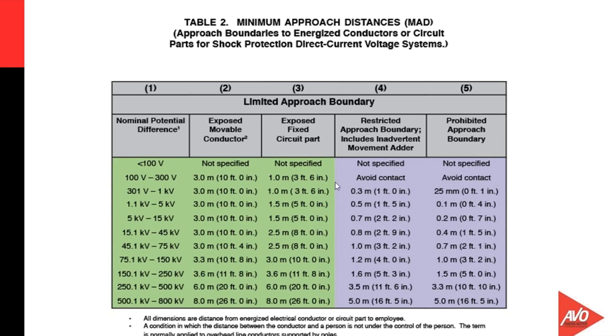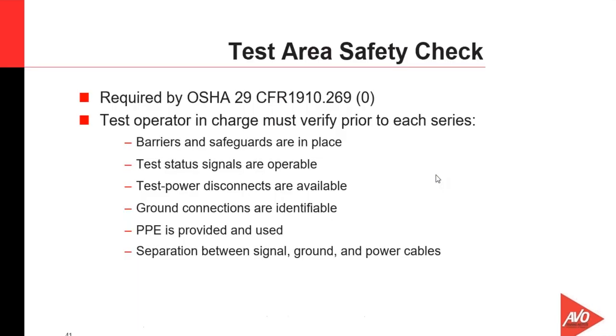Okay, I separated this out as a separate discussion. We have included it, but I wanted to make sure we covered this. This is a very detailed thing that's covered in 1910.269 Section O in the Transmission Distribution Generating Standard. It has to do with the test operator in charge verifying before each series of tests that the test area is safe. And OSHA has listed at a minimum things here that they expect that we would look at to make sure the test area is safe for the test technicians as well as others in an area outside the test area.